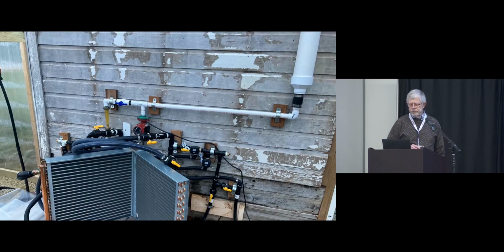Doing that required quite a few valves and fittings, and there's electronic solenoid valves, and you can see the flow meter and the pump, and it just gets to be kind of a busy wall. On the right there is a 4-inch diameter PVC pipe. That's just an expansion tank substitute, and it's a place where you can add ingredients. So I got it all set up, had 2 heat exchangers. I think they're 2 foot by 2 foot heat exchangers, 3-row, and started the system going and got very disappointing flow rates.